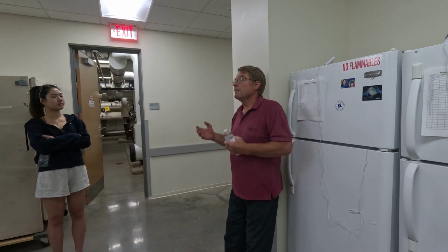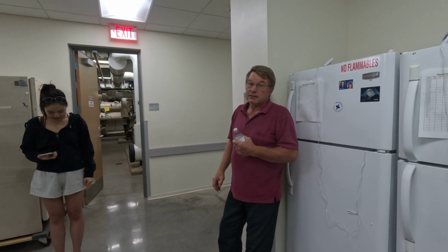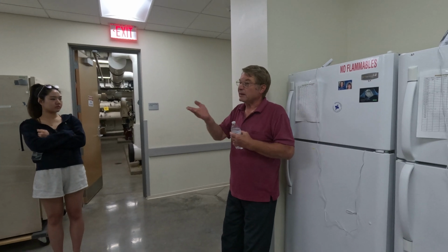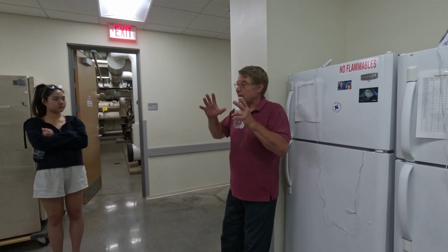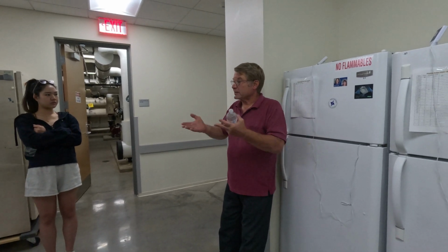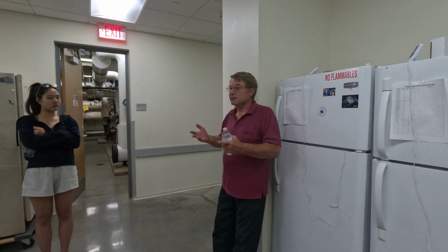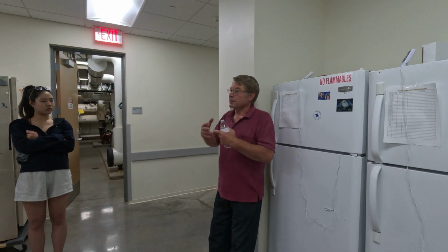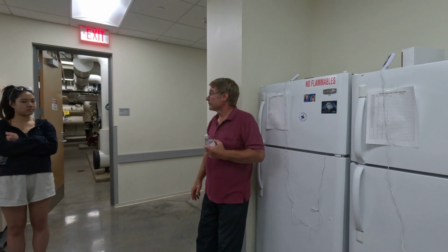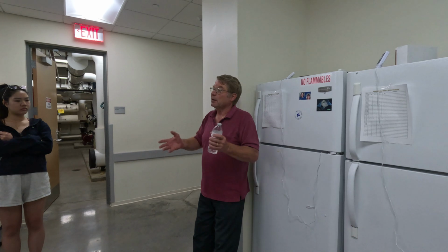With our building, all of our discharge air year-round, doesn't make any difference, is about 58 degrees. Then it's distributed throughout the building, and rather than reheat at every single office, it's got larger reheat coils built into the system, and it brings it up in areas rather than individually, which is more efficient. And then the chill beam is more efficient to cool than it is to heat. So when it gets to your office, it's actually cooled down to a temperature that's comfortable for you. So that's one big difference between our building, the newer version, and the older buildings.